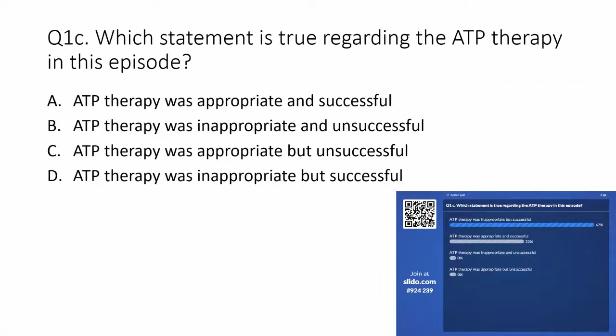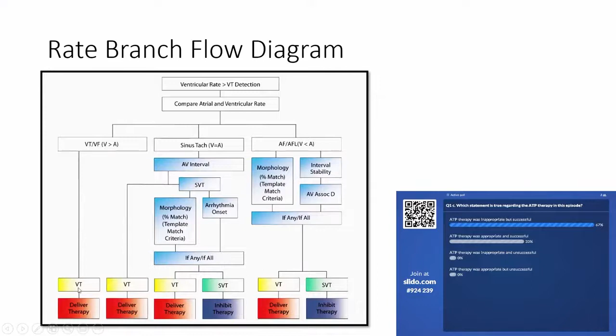So if you go back to the Abbott discrimination or rate branch flow diagram in Abbott ICDs and CRTDs, the device looks at the ventricular detection rate and then compares the atrial and ventricular rates in patients who have dual chamber ICDs or CRTDs. And if it finds that the ventricular rate is higher than the atrial rate, it straight away diagnoses it as ventricular tachycardia and delivers the therapy, and does not apply the SVT, VT discriminators as in the present episode.